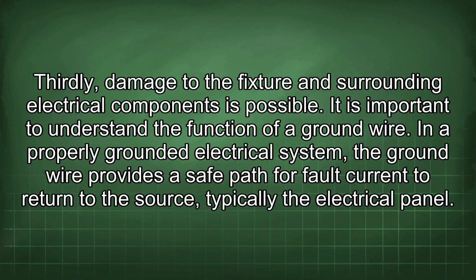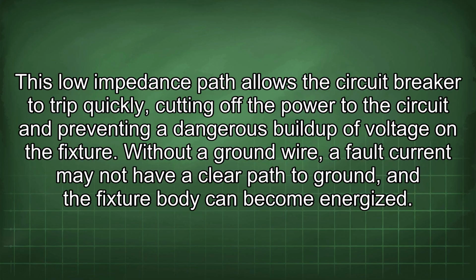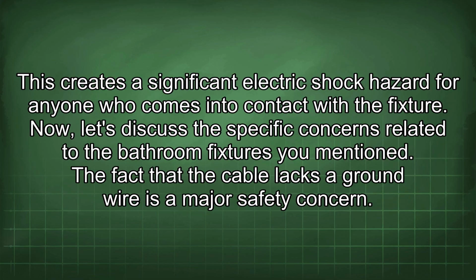It is important to understand the function of a ground wire. In a properly grounded electrical system, the ground wire provides a safe path for fault current to return to the source, typically the electrical panel. This low impedance path allows the circuit breaker to trip quickly, cutting off the power to the circuit and preventing a dangerous buildup of voltage on the fixture. Without a ground wire, a fault current may not have a clear path to ground, and the fixture body can become energized. This creates a significant electric shock hazard for anyone who comes into contact with the fixture.